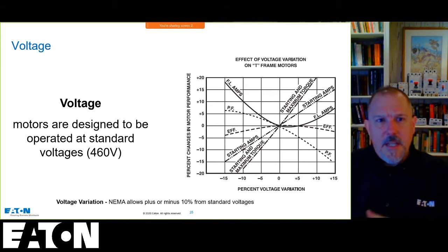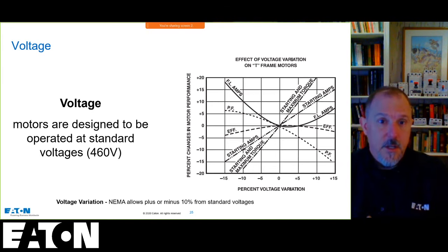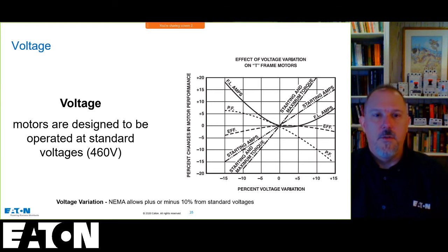So that whole application of voltage, there's a lot of different parameters that will impact the performance of that. And I like this NEMA. NEMA allows a plus or minus 10% on standard voltages, but this shows you that percent voltage variation will impact the full load amps, the starting amps, and the efficiency and power factor of a motor.